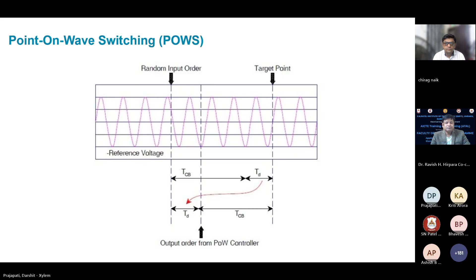So, these are the list of the parameters. From random input commands to synchronized breaker operations, the target delay is derived from different circuit breaker parameters with operation time factors. You can see the line frequency, that is the frequency of the system, will be considered as the system reference. And then the delay which we have seen over here will be introduced by all the parameters which are listed from second onwards. So that is the SF6 gas pressure or density.